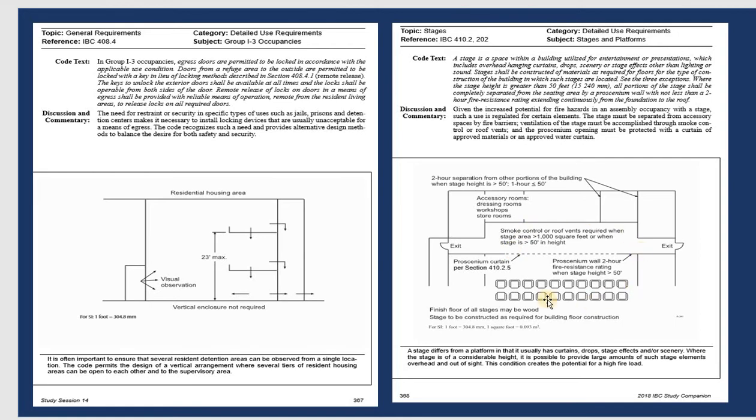And if you have, this is the stage, and they have the roof for the stage. For example, the stage with the curtain, and they need to have 2 hours for the fire resistance rating in that wall, in the level from the curtain, the access both sides, and after that inside here between the room in the back side from the stage, they need 2 hours separate. That means the wall right here, the wall right here should be 2 hour construction.